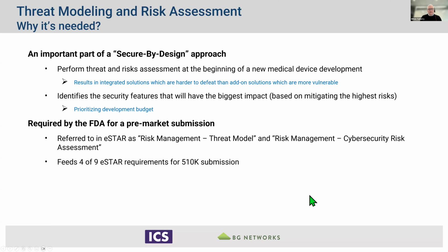Also, it's required by the FDA for pre-market submission. In eSTAR, which is the FDA's system for submitting 510(k)s, it's referred to as risk management threat model or risk management cybersecurity risk assessment. This basically feeds several of the eSTAR requirements for 510(k) submission, so it's usable immediately from the time you submit.